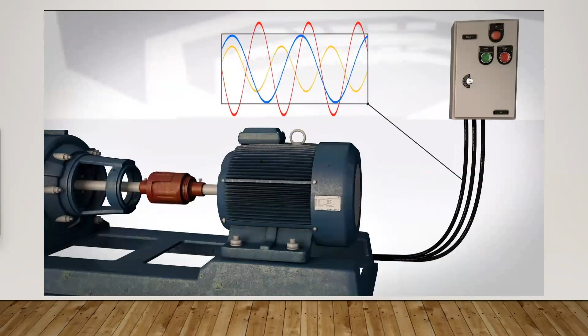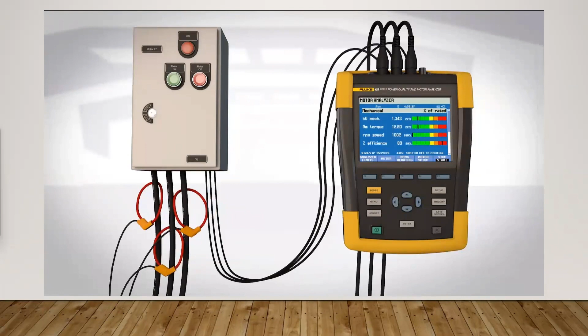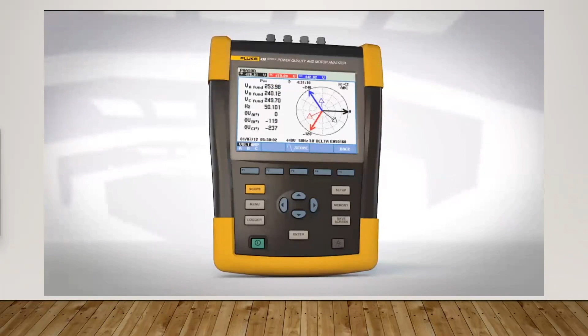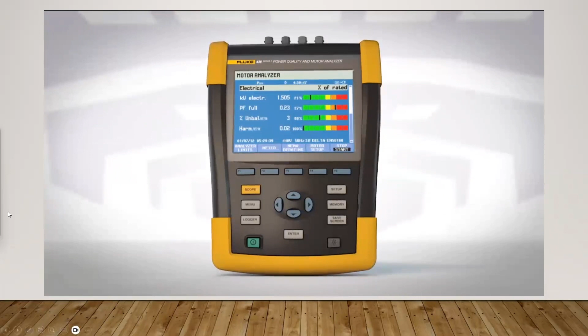Power quality issues, such as unbalance and harmonics, can cause motors to run hot, eventually stressing windings and accelerating failures. Motor failures lead to costly downtime, and the cost of waste associated with inefficient motors adds up. When testing direct online motors with the new Fluke 438, you get both power quality information and mechanical performance data in the same test with a single tool.